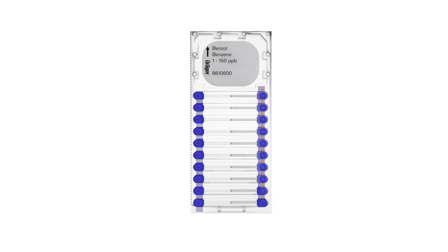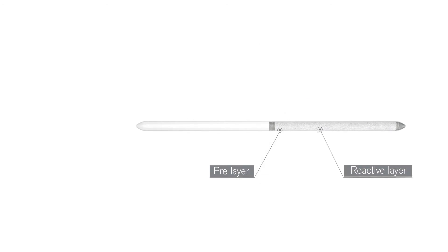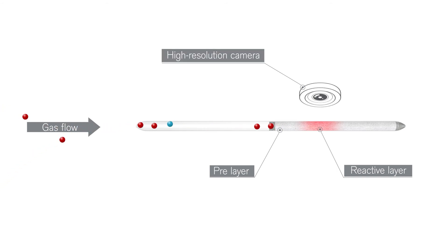The sensitive microtubes are based on colorimetric chemical sensors. They consist of multiple outer layers and reactive layers that allow for selective testing. The outer layers serve as a filter — they filter out other substances that occur at the worksite, while the hazardous substance being measured triggers a chemical reaction with the reactant system. As a result, the microtube changes color. A high-resolution digital camera in the optical electrical analysis device monitors this reaction and analyzes the discoloration, which is often not visible to the human eye.